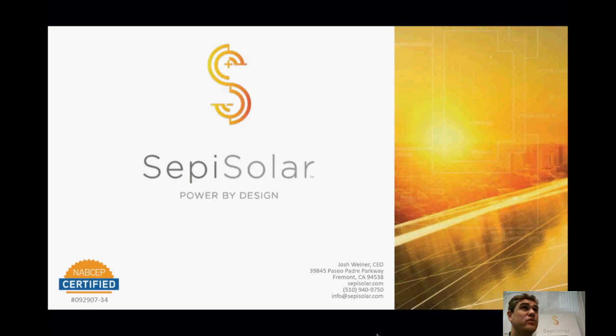In that case, you follow the rules of line side points of connection, and there is an exception for line side or supply side points of connection for storage. Again, solar was a bit more straightforward because it was just a supply source. But with storage, it's a load and a supply source, so it's very prudent and important to treat that battery as a load, especially if you're going around the main breaker with a supply side point of connection. There's much more pressure to get the engineering right in that situation.